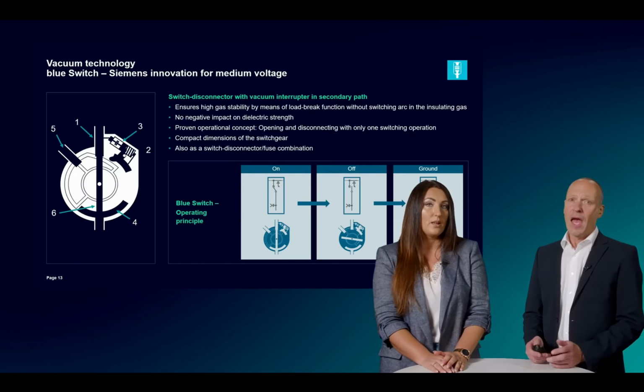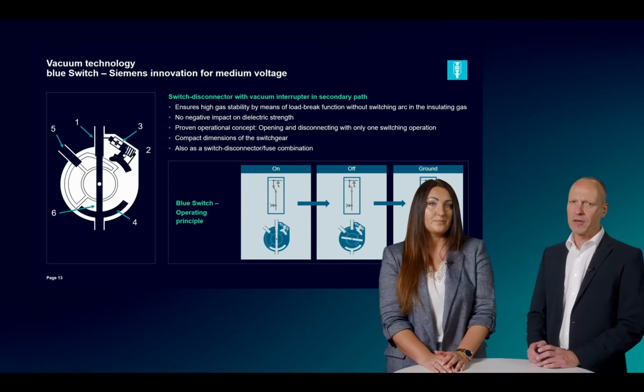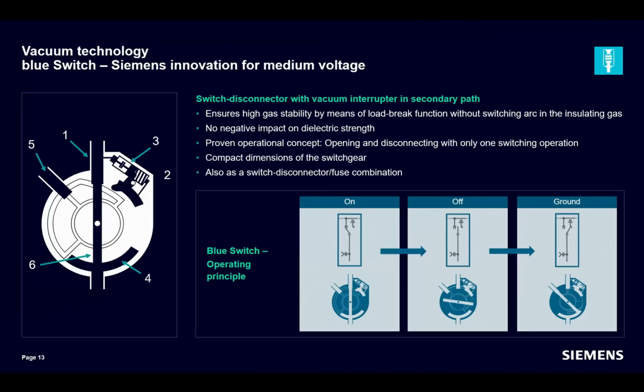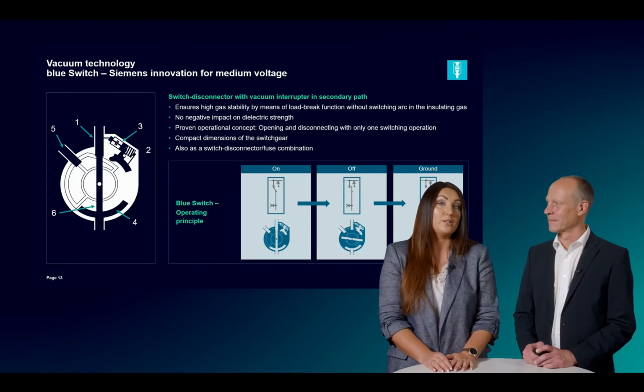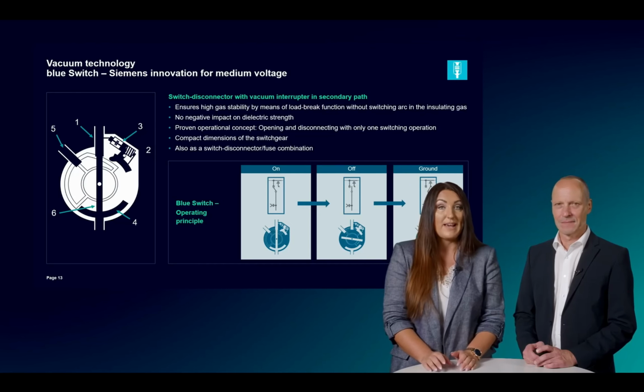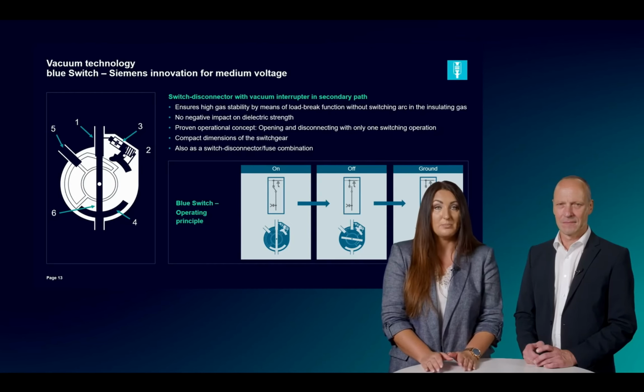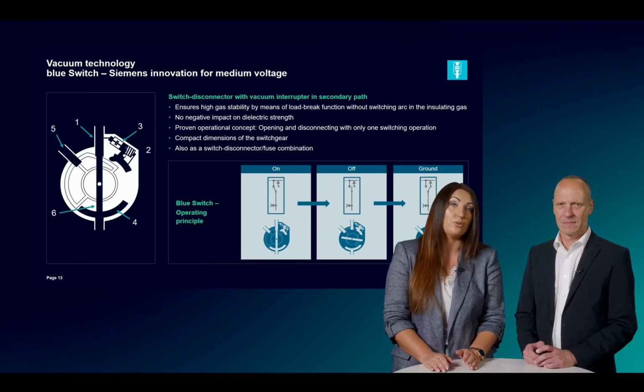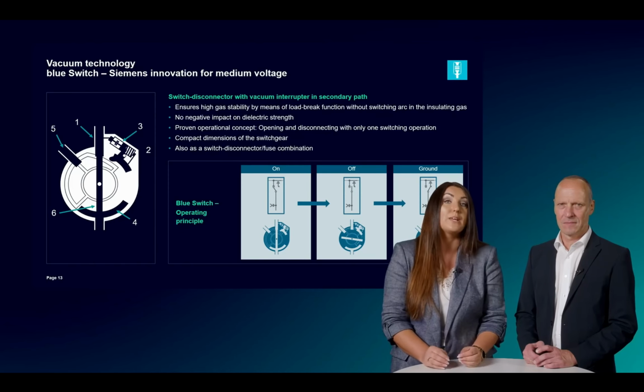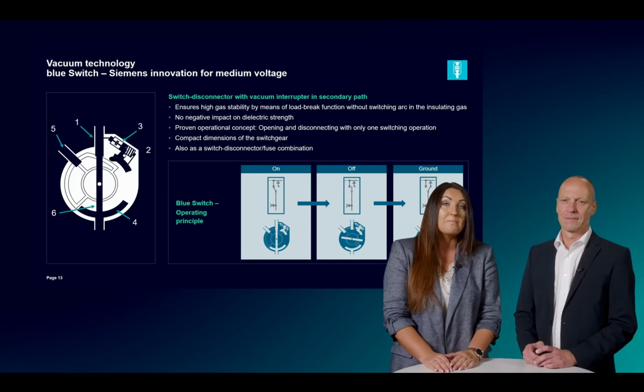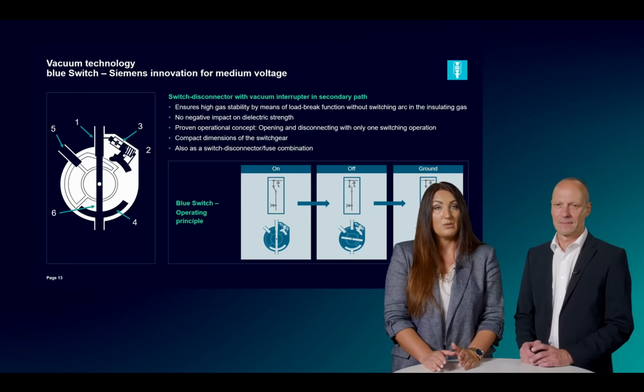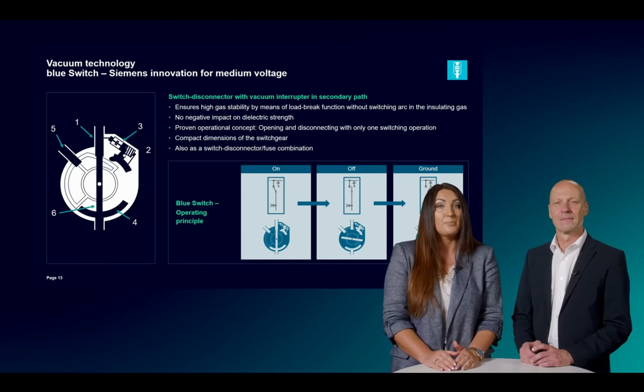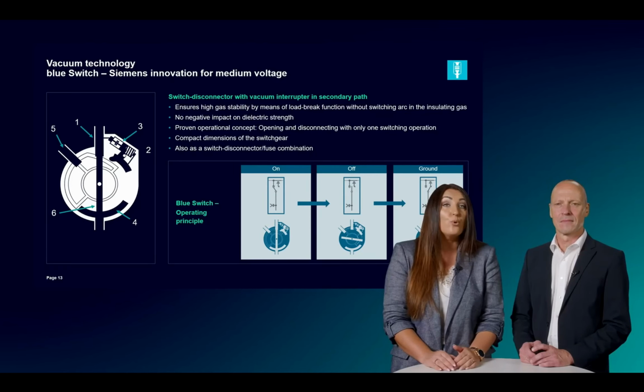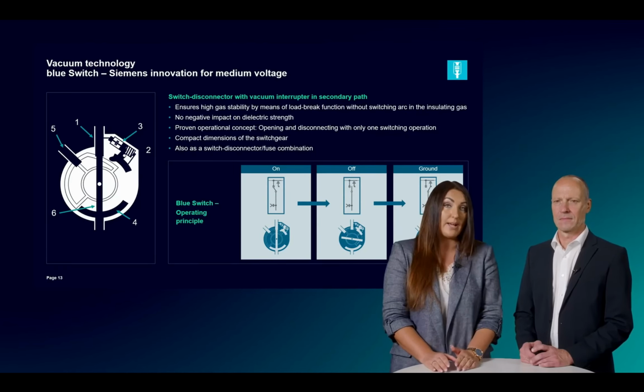Oh, impressive. And what is the exact role of the vacuum interrupter in the auxiliary path? Well, Bernd, it's the current interruption during a breaking operation. This very small vacuum interrupter is stressed by current only for a short period of time during a breaking operation. So in switching position on, the vacuum interrupter and the auxiliary path are not active and no current flows through this path.